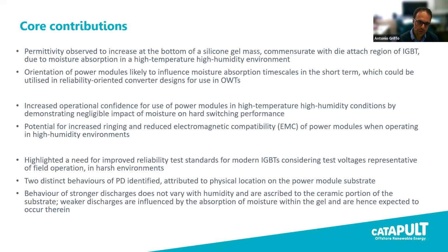We have demonstrated that the short-term effects of humidity ingress on switching performance of power converters are probably not significant. Nevertheless, there are significant concerns on the long-term reliability of power modules when they are subject to this harsh environment. And in particular, we have demonstrated that partial discharge is significantly affected by humidity. Therefore, this is a consideration that needs to be taken into account in long-term reliability investigation of power modules.